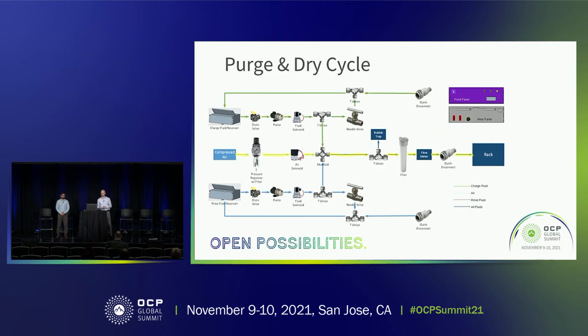The last cycle I want to touch on here is the purge and dry cycle. So in this case, compressed air, that could be maybe facility air, compressed air within the cart itself, maybe compressed nitrogen. But ultimately, the key point here is having some sort of pressure regulator and filter for that air so that you are not introducing contaminants to your system, and then it goes out through that same outlet through the rack.